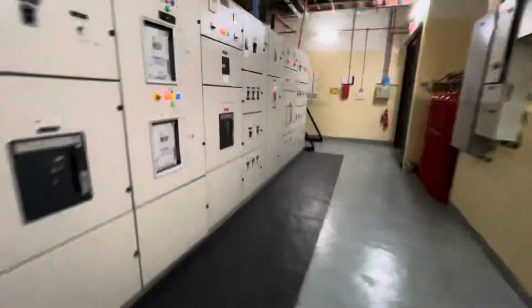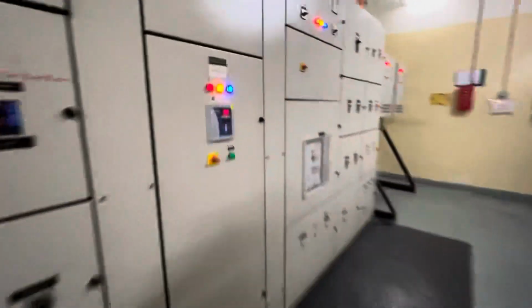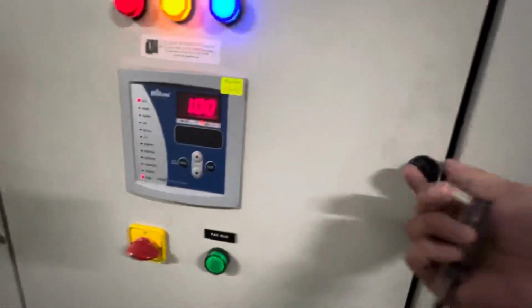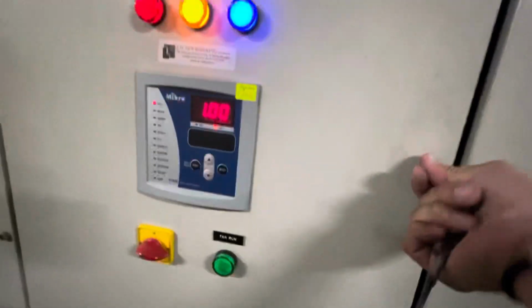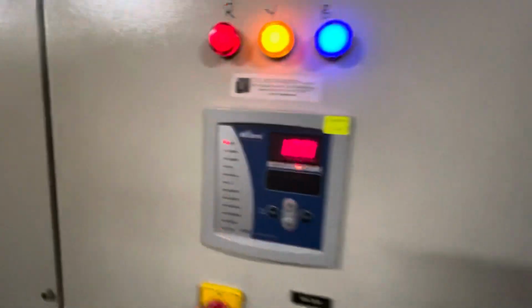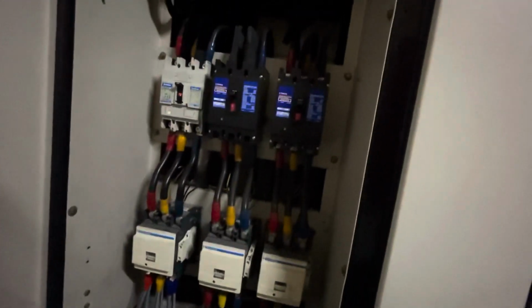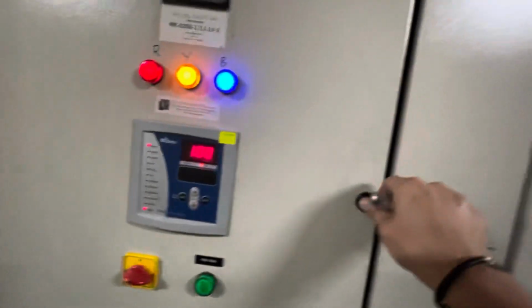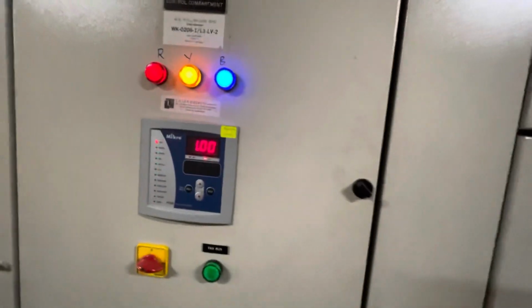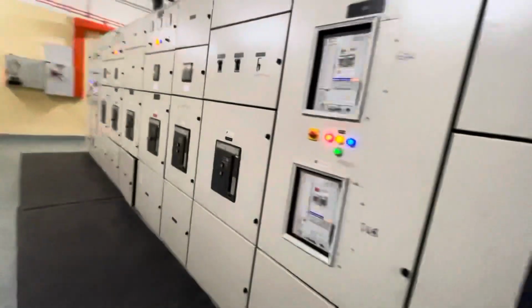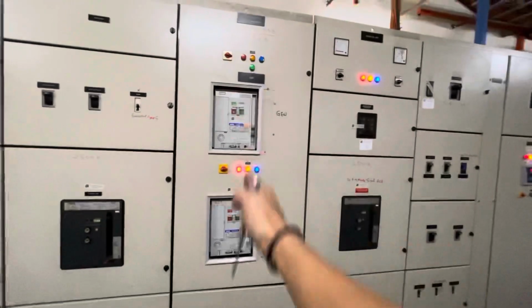Alright, after that, let's check the MSB number 2 capacitor bank panel. The power factor currently is at 1.00. Here we don't have any step energized. However, I'm going to check whether there's any cable burn or any tripping at the MCCB. No tripping. Okay, let's close back.